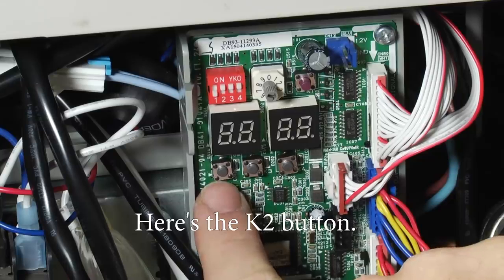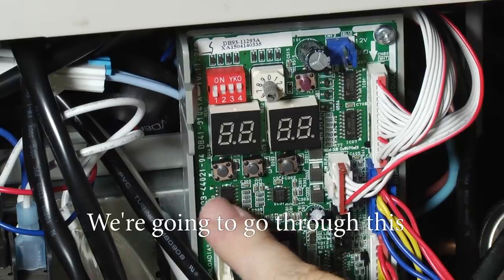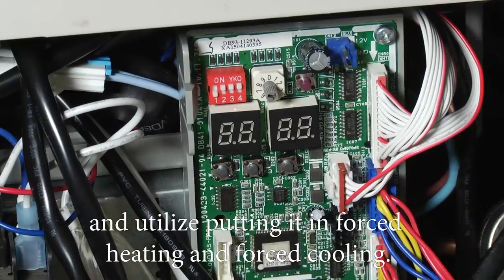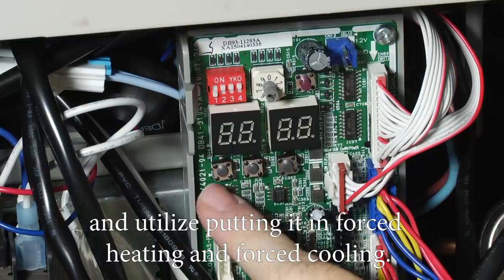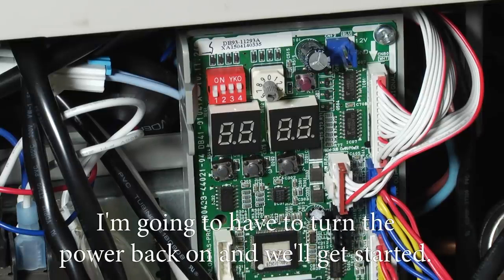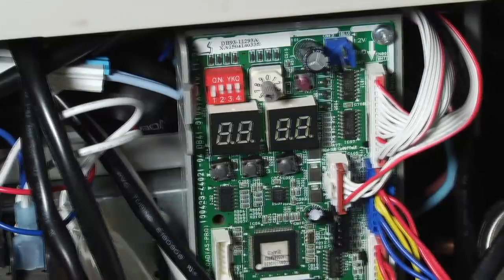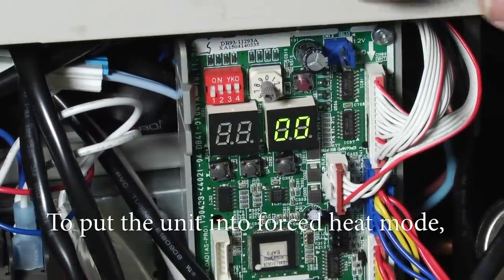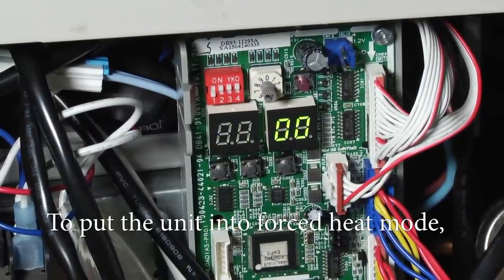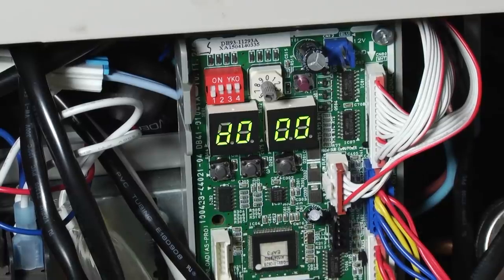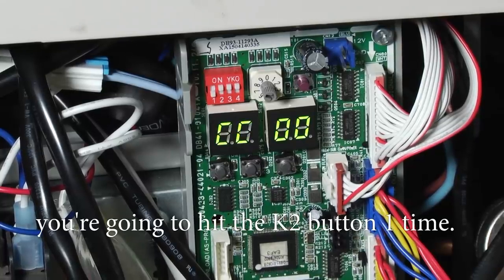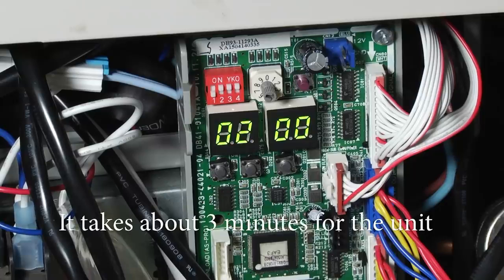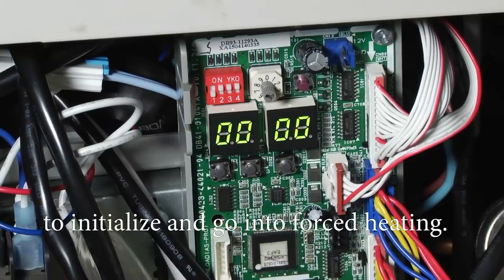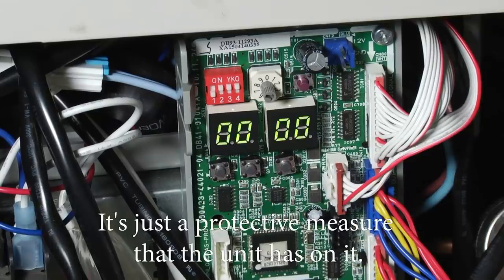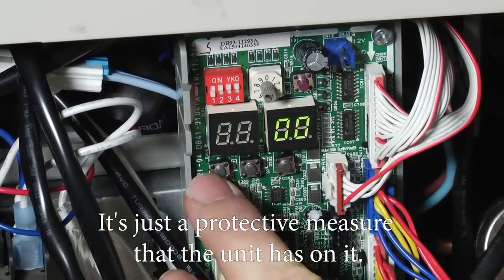Now here's the K2 button. We're going to go through this and utilize putting it in force heating and force cooling. I'm going to have to turn the power back on and we'll get started. Okay, so to put the unit into forced heat mode, you're going to hit the K2 button one time. It takes about 3 minutes for the unit to initialize and go into forced heating. It's just a protective measure the unit has on it.